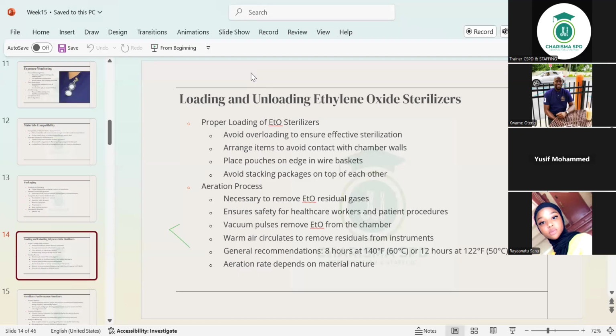We have wire baskets that we use so that if your sterilizer is one of the big ones, your pouches will have to go into those wire baskets because they don't have shelves that will contain your pouches. So you arrange them in the order that I've told you, like in a book tray. You arrange them paper to plastic, paper to plastic, like that. Arrange them nicely so that the basket is what you're going to put in the autoclave. All right? It's not a big thing. When you go there, you see it and you understand. You see those baskets all over, but they are used for things like pouches. You may have a lot of pouches to sterilize, so by organizing it that way, it makes it easier.